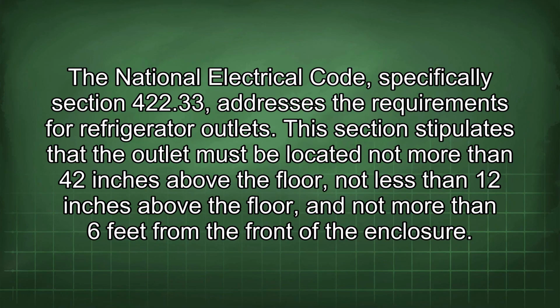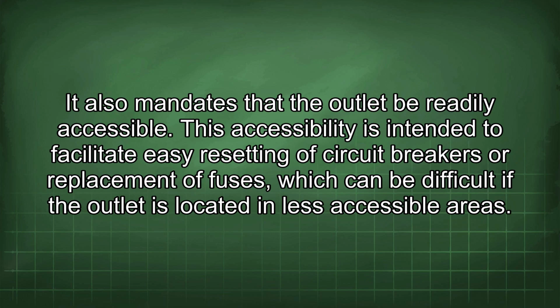The National Electrical Code, specifically Section 422.33, addresses the requirements for refrigerator outlets. This section stipulates that the outlet must be located not more than 42 inches above the floor, not less than 12 inches above the floor, and not more than 6 feet from the front of the enclosure. It also mandates that the outlet be readily accessible.